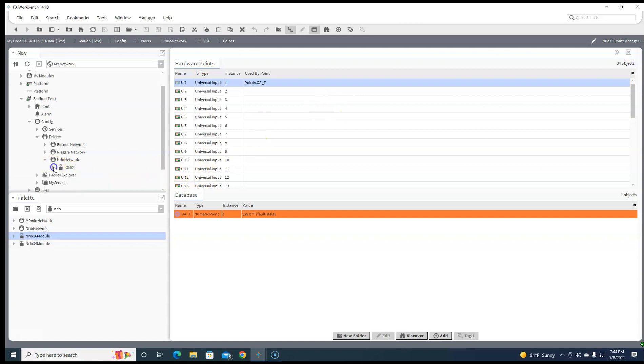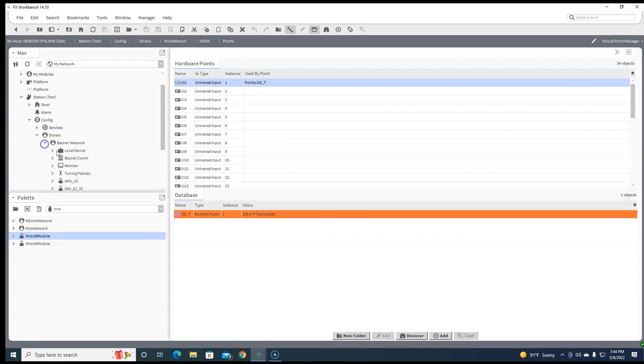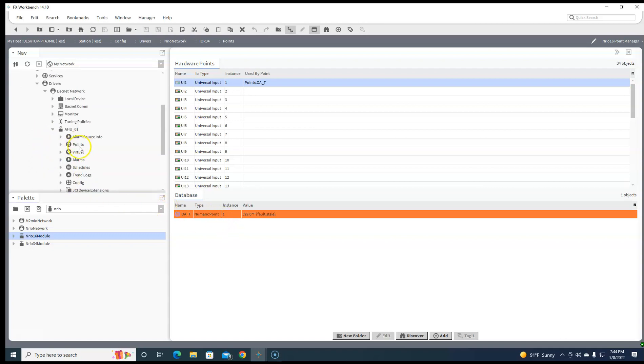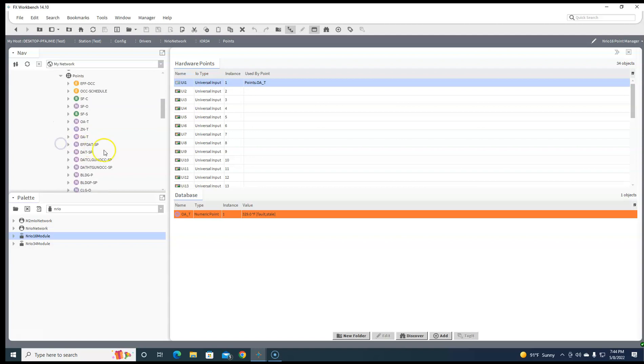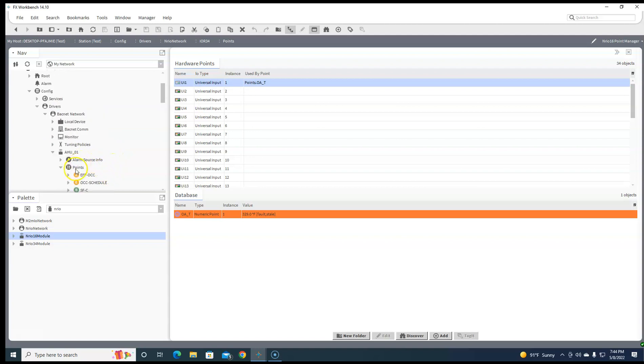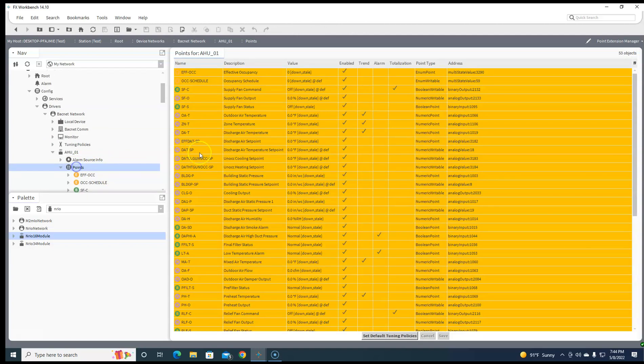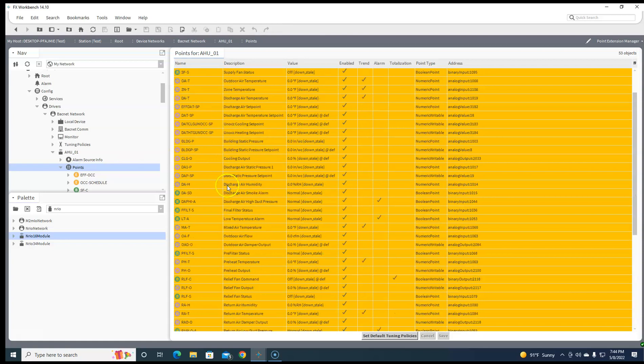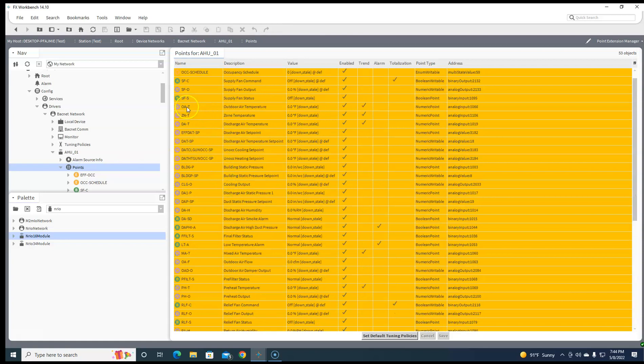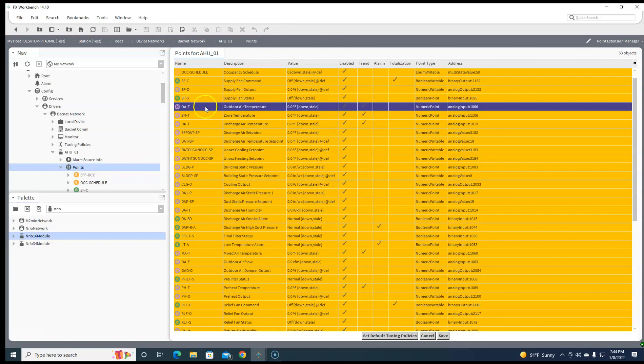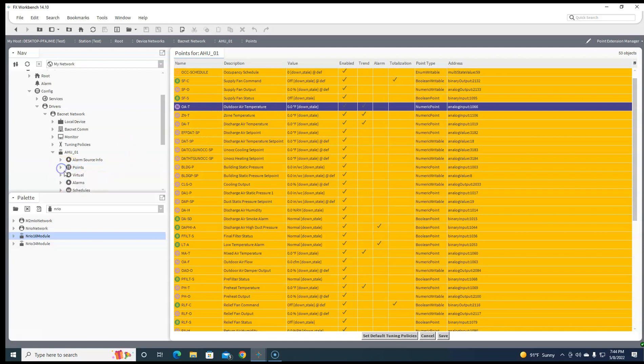But what we could do there is we could global share that point into any of the AHU points. So there's an outdoor air temperature, but that's going to be a hardware input too.